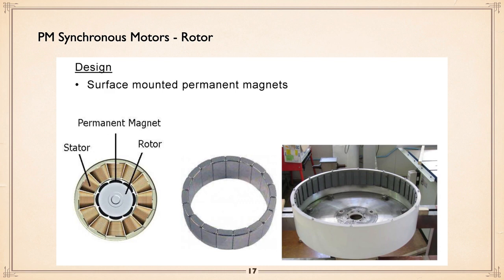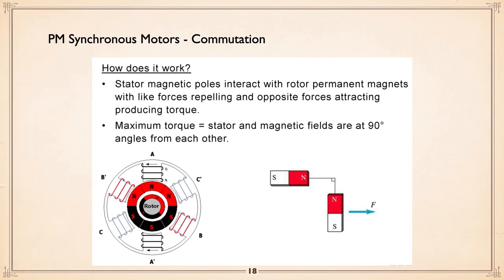Now, synchronous motors, which is what permanent magnet motors are. With a permanent magnet, you don't have to worry about generating the magnetic fields within the rotor. They are using permanent magnets to do it. Okay? So if you look at this drawing, the little black things are the permanent magnets stuck on the rotor, and the stator outside is essentially identical to what you would get with an induction motor. And again, same concept as the induction motor, except it's set to go, so to speak. The magnetism is always there.